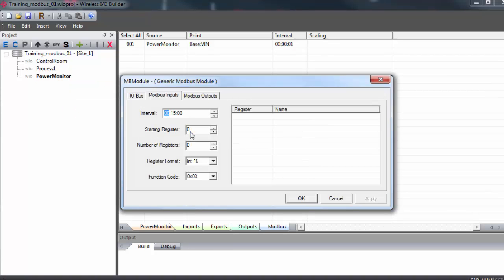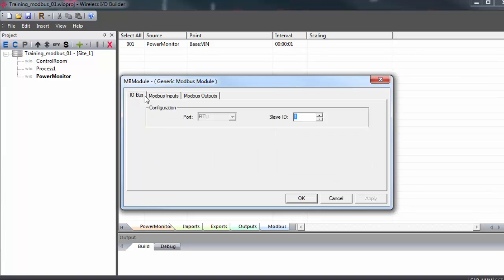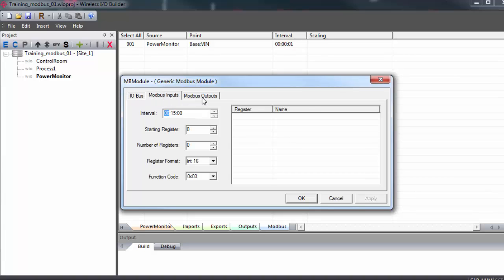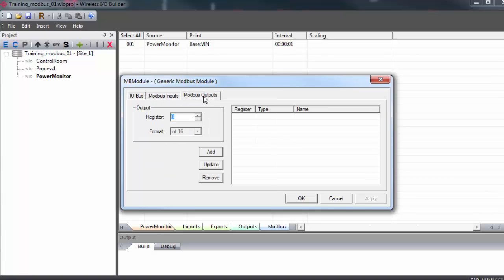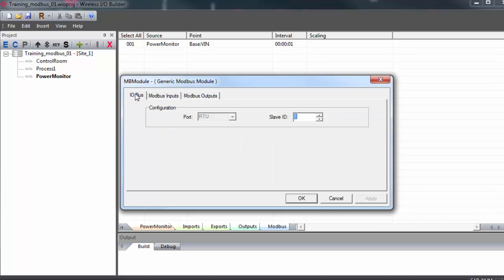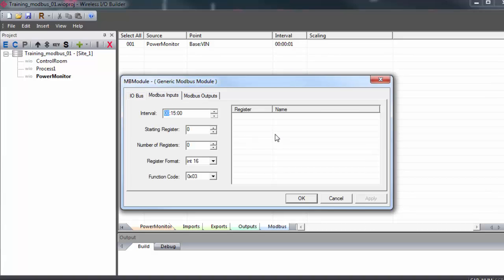And here we have our module window where we will configure all our communications with the Modbus power monitor. You can see the tabs we have at the top here. First, we'll go to the I.O. bus tab and enter in the slave ID of the Modbus device that we're connecting to. My power monitor is at slave ID 3.